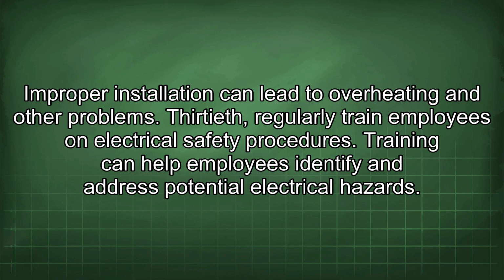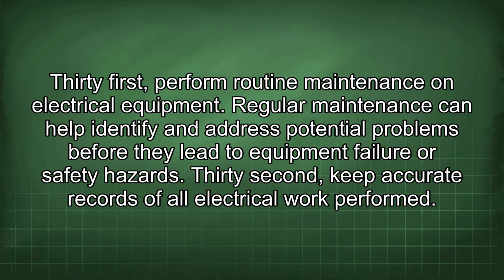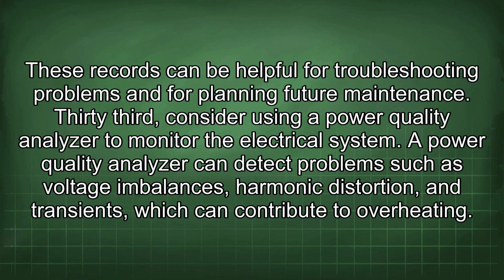30th, regularly train employees on electrical safety procedures. Training can help employees identify and address potential electrical hazards. 31st, perform routine maintenance on electrical equipment. Regular maintenance can help identify and address potential problems before they lead to equipment failure or safety hazards. 32nd, keep accurate records of all electrical work performed. These records can be helpful for troubleshooting problems and for planning future maintenance. 33rd, consider using a power quality analyzer to monitor the electrical system. A power quality analyzer can detect problems such as voltage imbalances, harmonic distortion, and transients, which can contribute to overheating.